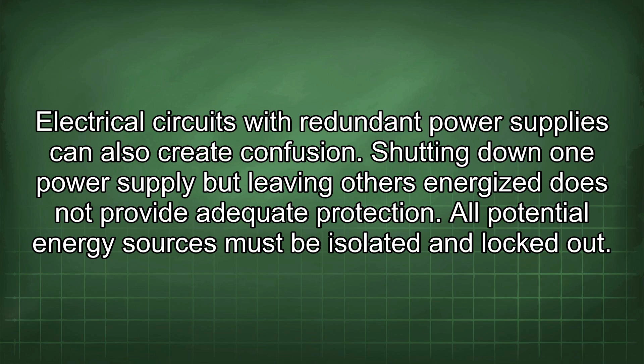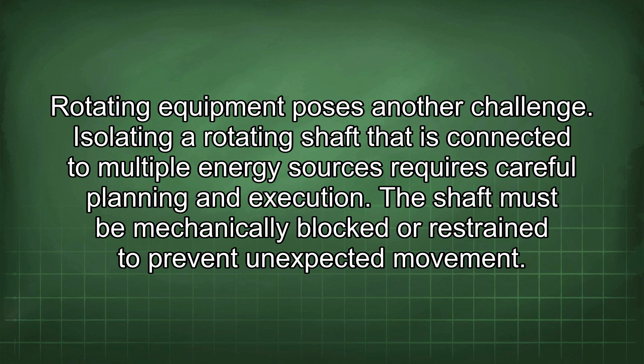Rotating equipment poses another challenge. Isolating a rotating shaft that is connected to multiple energy sources requires careful planning and execution. The shaft must be mechanically blocked or restrained to prevent unexpected movement. Portable equipment raises questions. Whether LOTO is required for portable equipment that is frequently moved depends on the specific circumstances. If the equipment is plugged into a standard electrical outlet and is not used in a hazardous location, LOTO may not be necessary. However, if the equipment is used in a wet or dusty environment or is connected to a high-voltage power source, LOTO is essential.